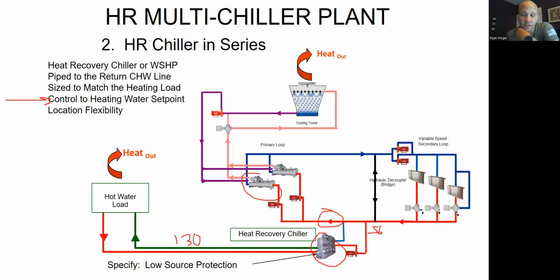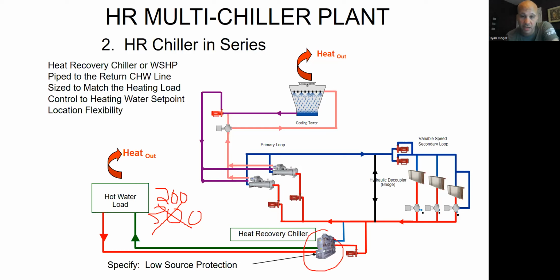Right. So in this particular example, let's do both of them for your question. Let's say that I size this for, I think I said earlier, 300 tons. And let's say for some reason it's a holiday weekend, or it's something else, and the hotel needs less. And it goes down to 200 tons. For whatever reason, it's 200 tons instead of 300 tons. This chiller would then have to ramp down. Right. And that's okay in this case. He ramps down, and instead of giving me X degree water, it's something slightly warmer.